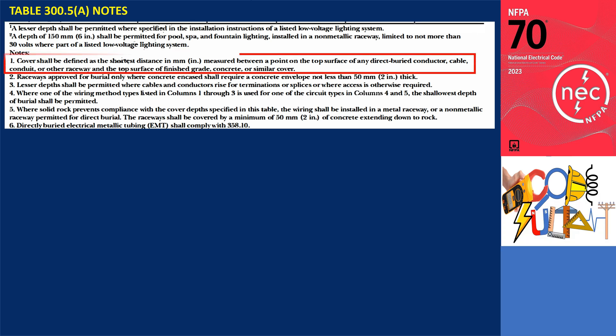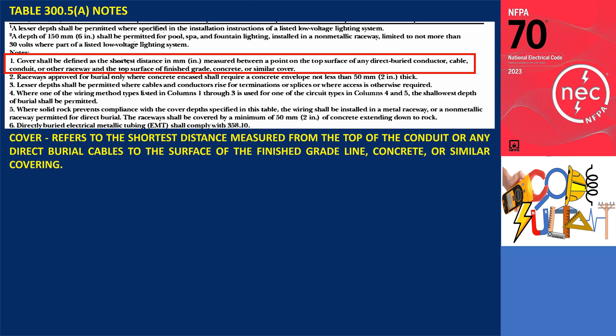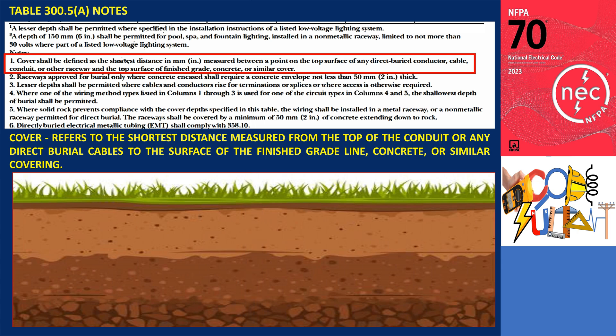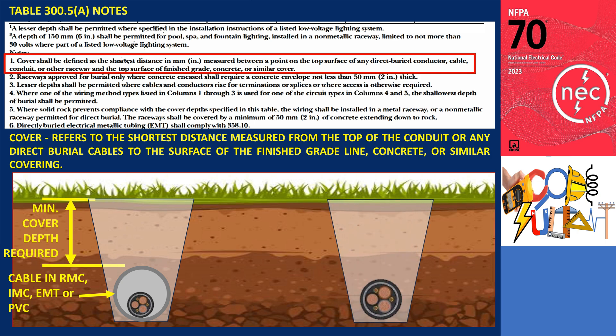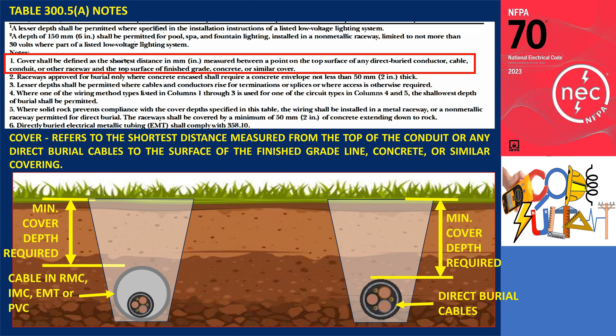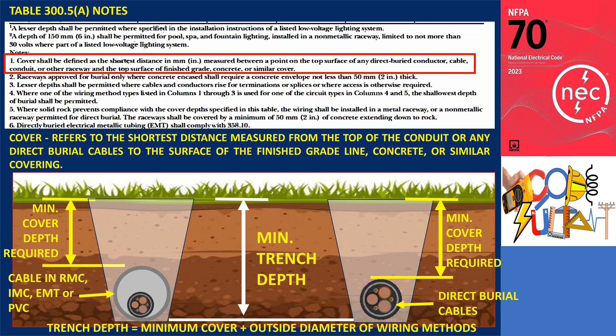For Note 1, cover shall be defined as the shortest distance in millimeters or inches, measured between a point on the top surface of any direct buried conductor, cable, conduit, or other raceway and the top surface of finished grade, concrete, or similar cover. For example, in a wiring method installed in RMC, IMC, EMT, or PVC, the depth shall be measured from the top surface finish grade line to the top of the conduit. For direct burial cable, the measurement is taken from the top surface of the cable. Therefore, the minimum trench depth must equal the required depth of cover plus any additional depth needed to accommodate the outside diameter of the cables or raceways being installed.